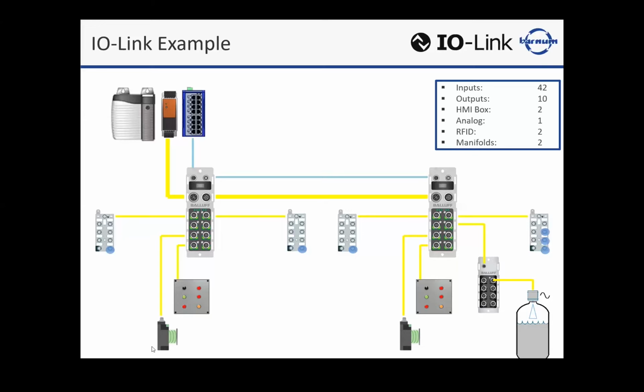Tags and readers. So these readers are now attached directly to the master. Eliminated the processor altogether. Eliminated that $2,500 processor that can only handle two heads. Here, if we wanted to, we could connect 8 RFID read-write heads directly to one master. Fantastic. And so our manifolds, again, those are now connected to IO-Link masters as well. Yes, correct. So let's do a cost analysis.